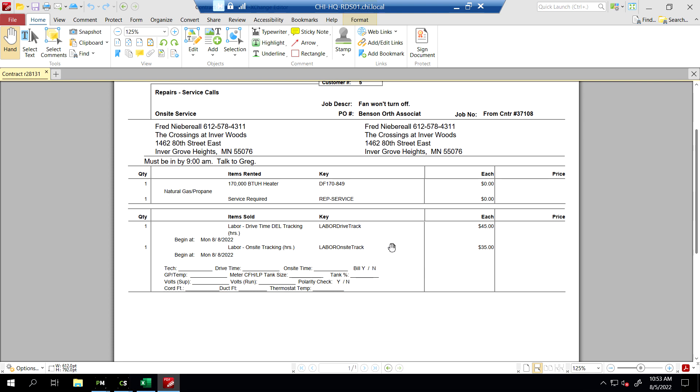Bill - yes or no. If the service person feels that this should be billed. Like, yep, they went in, they had bad low voltage, they're at 109 volts. We need to be at 110 volts. So they'll circle yes as a charge. Division managers are the ones who okay these charges.